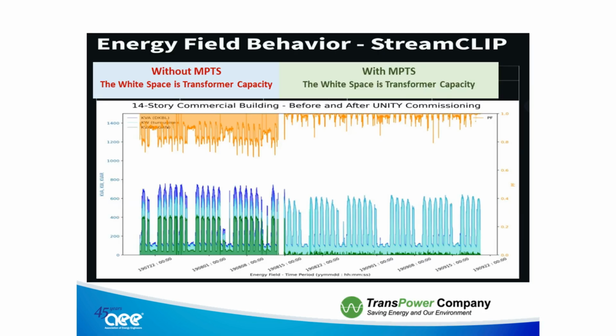The live, recorded data indicates a decline in power issues when MPTS was turned on, with the green color symbolizing a significant reduction in dirty power to a minimum. The increase in the white area signifies that the decrease in dirty power has reduced the load on the utility transformer.